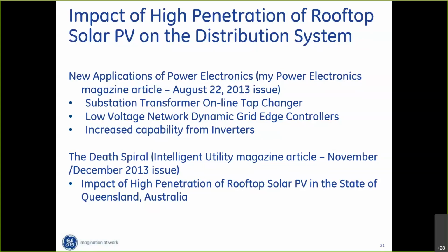The tap changer in the substation, before any home installed solar panels, was operating 5 to 10 times per day. Now this tap changer was operating well over 100 times per day.